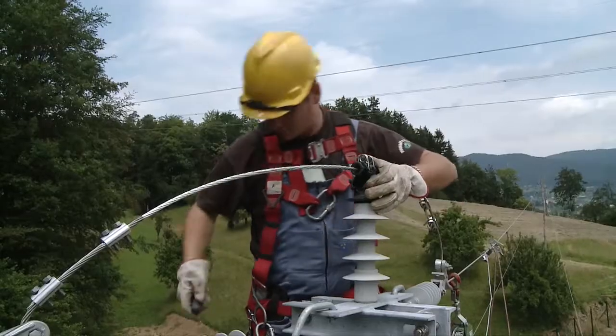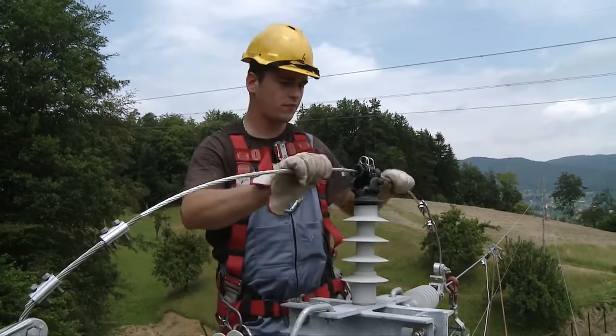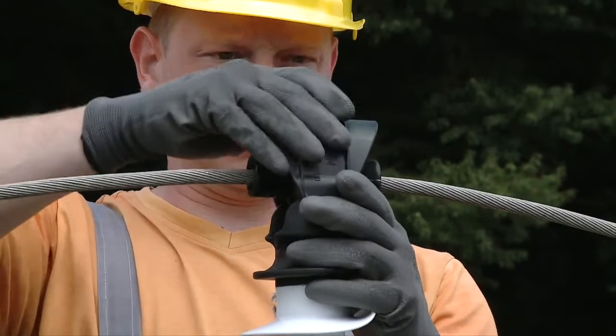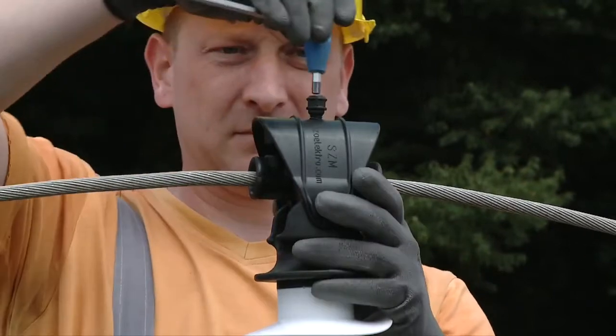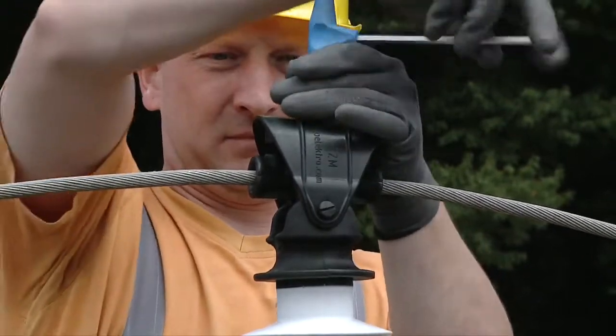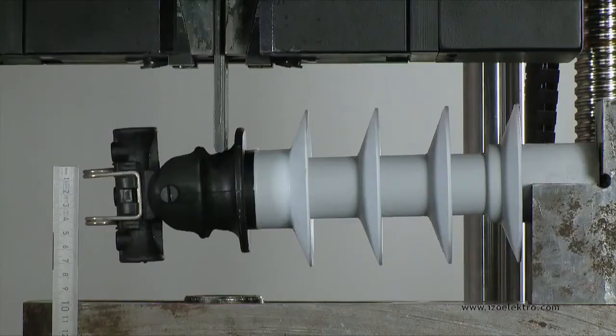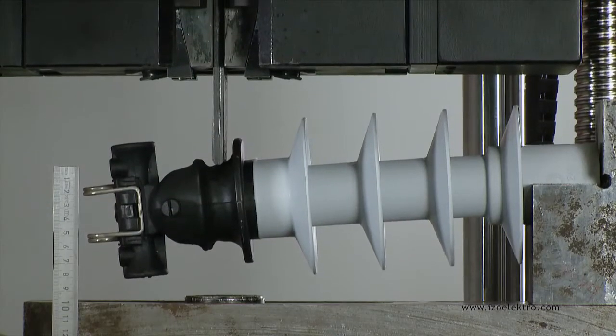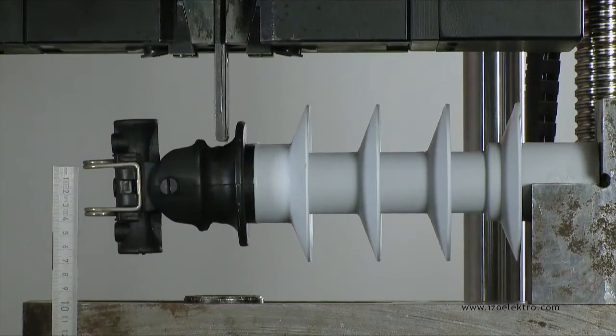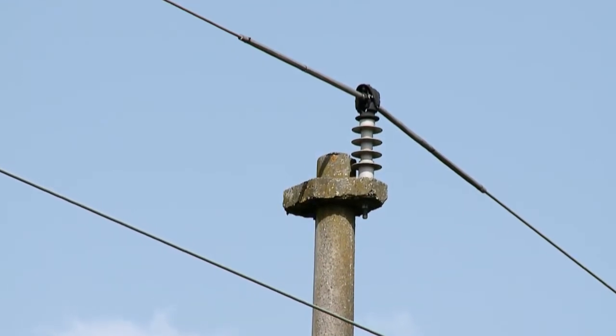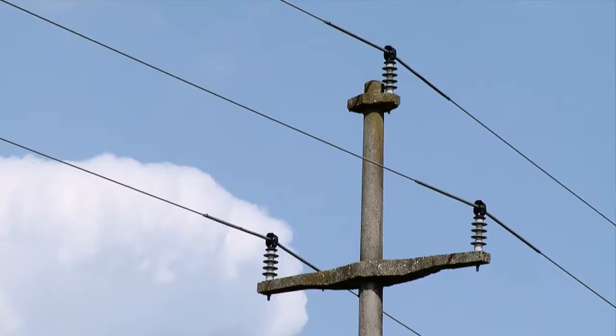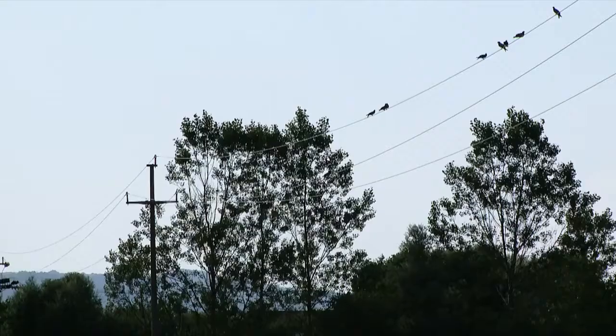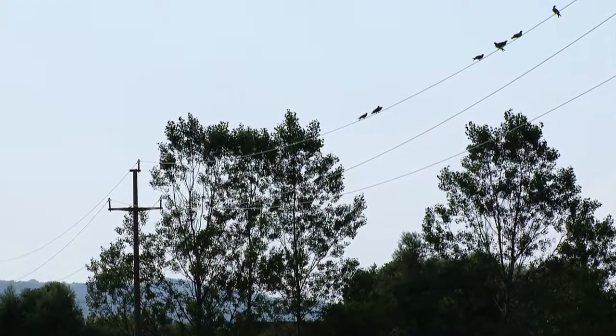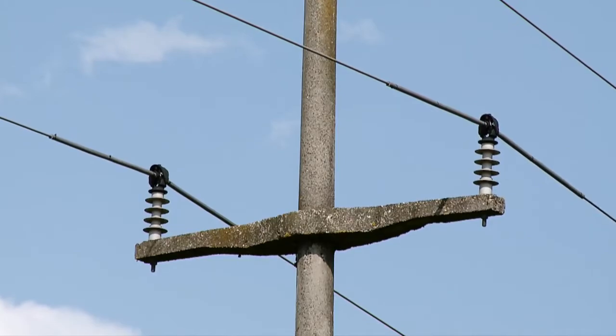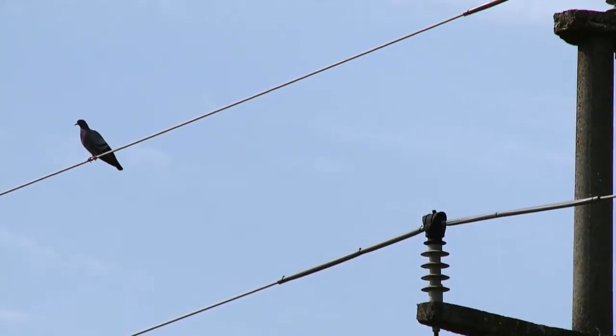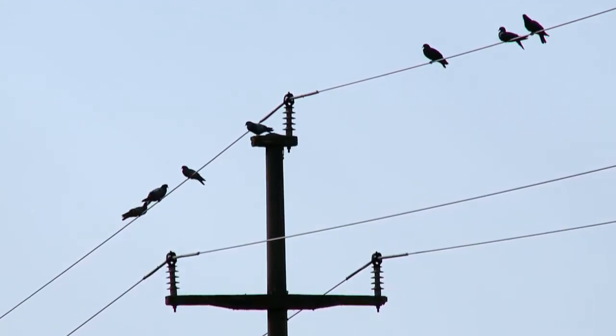In order to improve the spring clamp's mechanical characteristics and versatility, we upgraded the insulator's top-end fitting with a protective cap, which enables an increase of the conductor's pull-out force in both horizontal and vertical directions. With an additional 1 meter long silicone coat added onto the bare conductor at each side of the insulator, the spring clamp is intended to completely secure the carrying poles and thus prevent short circuits. This solution also provides protection for birds.